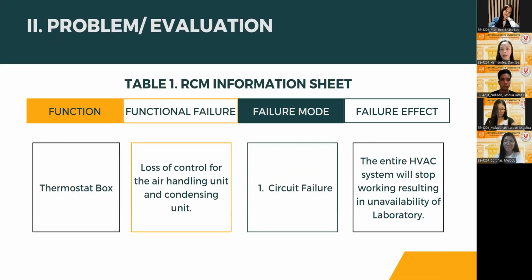Next is the thermostat box. Since the thermostat box controls the entire operation of the HVAC system, the possible functional failure is its inability to control its counterparts. This may be caused by circuit failure. If the thermostat malfunctions, the HVAC system may start and stop randomly. As a result, rooms closer to the HVAC system receive more cool or hot air, while those farther away receive little or none.